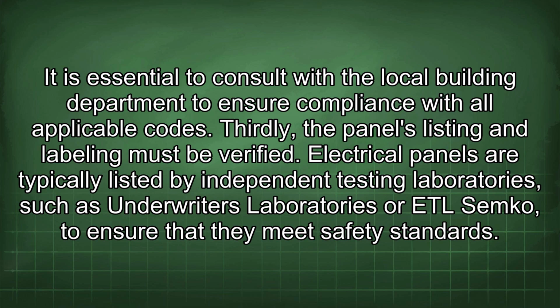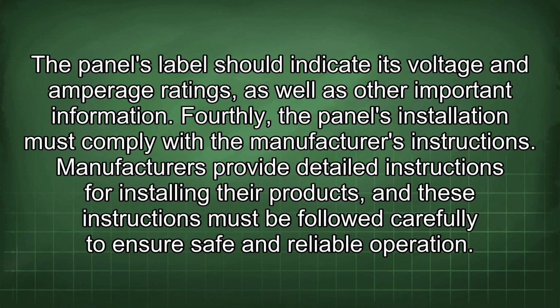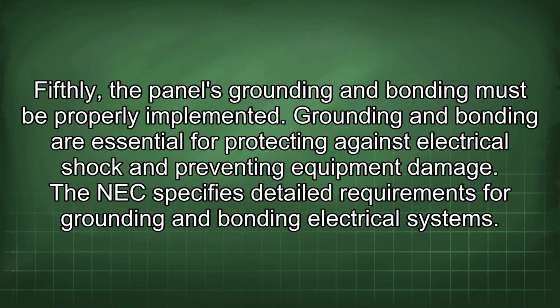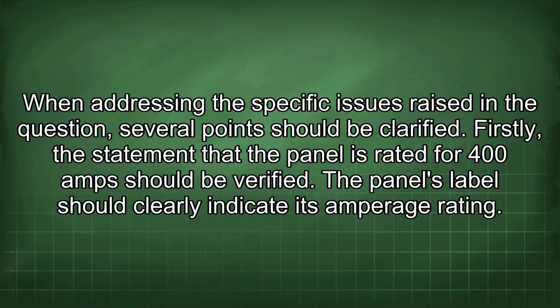Thirdly, the panel's listing and labeling must be verified. Electrical panels are typically listed by independent testing laboratories, such as Underwriters Laboratories or ETL-SEMKO, to ensure that they meet safety standards. The panel's label should indicate its voltage and amperage ratings, as well as other important information. Fourthly, the panel's installation must comply with the manufacturer's instructions. Manufacturers provide detailed instructions for installing their products, and these instructions must be followed carefully to ensure safe and reliable operation. Fifthly, the panel's grounding and bonding must be properly implemented. Grounding and bonding are essential for protecting against electrical shock and preventing equipment damage. The NEC specifies detailed requirements for grounding and bonding electrical systems. When addressing the specific issues raised in the question, several points should be clarified.